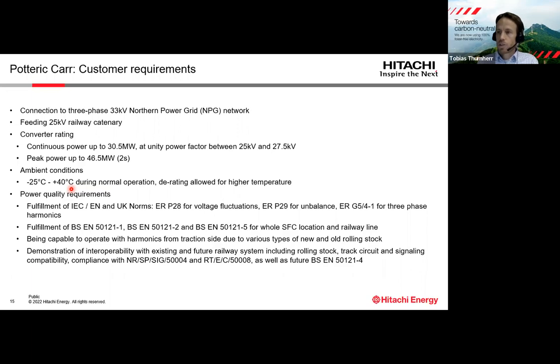This slide shows the customer requirements. I've mentioned connection to the 3-phase 33 kV grid and to the 25 kV railway catenary. Converter rating is continuously up to 30.5 megawatt, and then an overload capability up to 46.5 megawatt for up to 2 seconds, with ambient conditions between -25 and 40 degrees during normal operation, and a derating allowed for higher temperature.